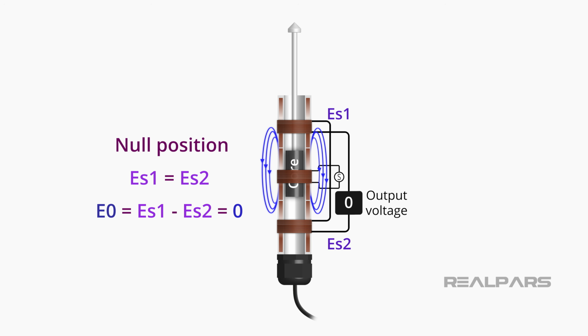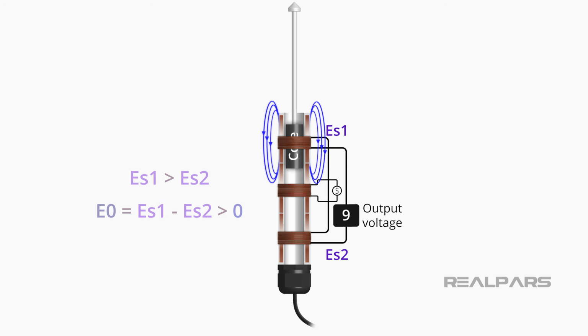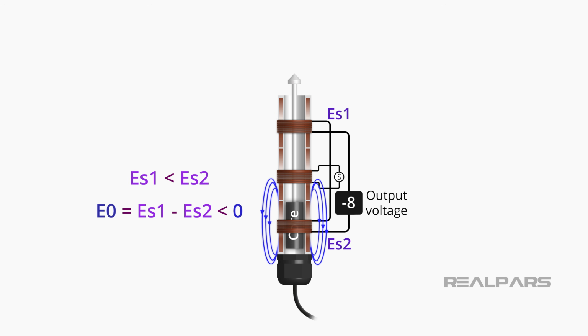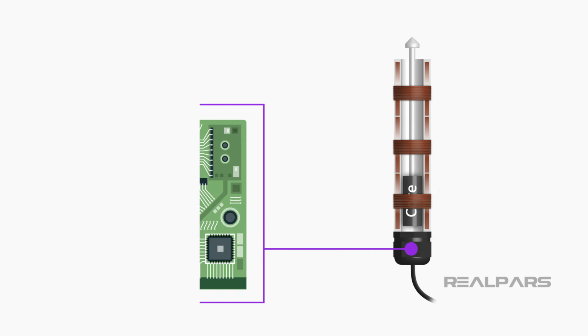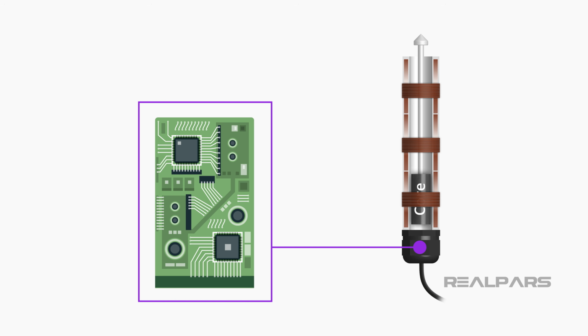When the core is positioned in the null position, the output signal is 0. Moving the core in either direction causes the output signal to increase. Current technologies allow for AC and DC LVDT sensors.